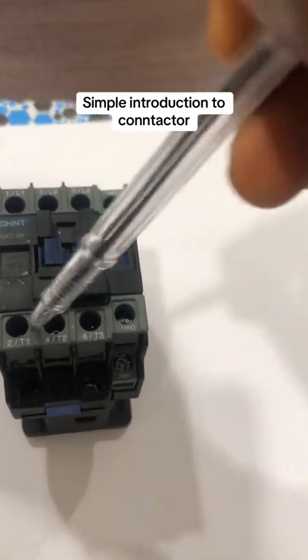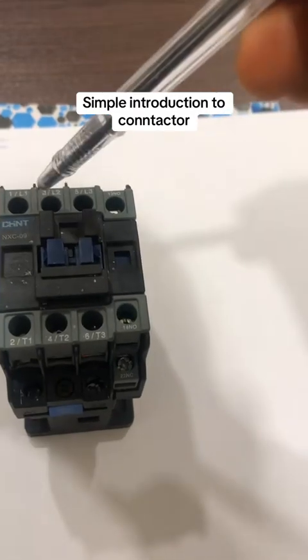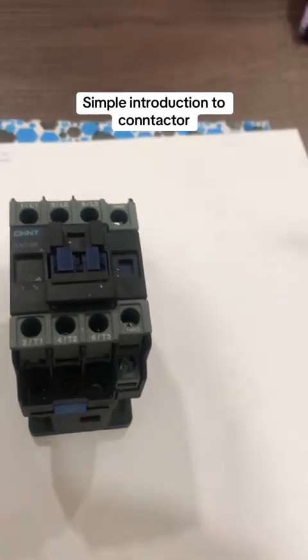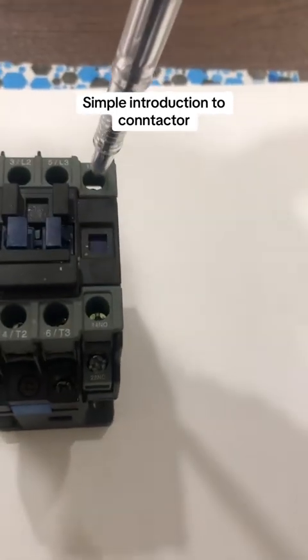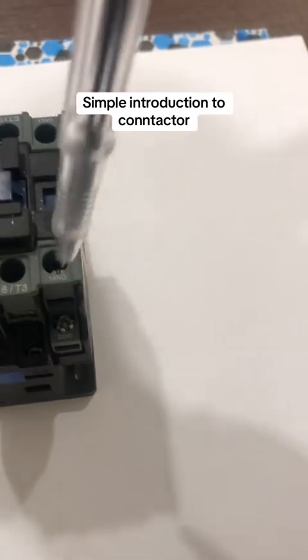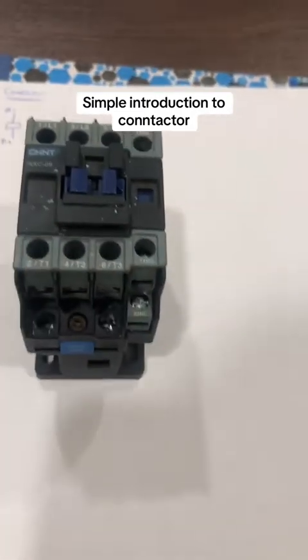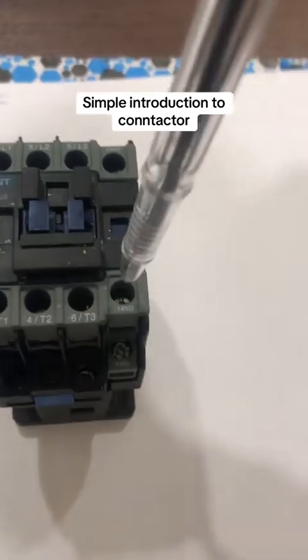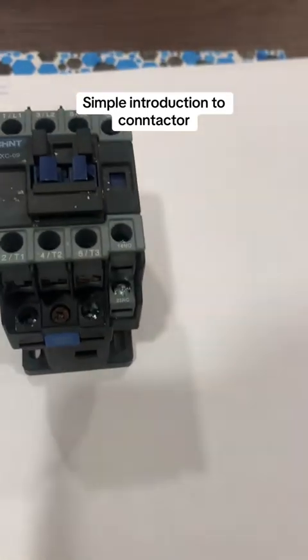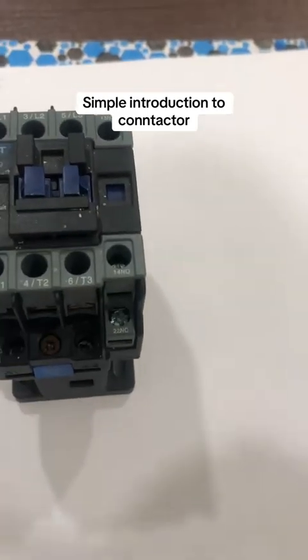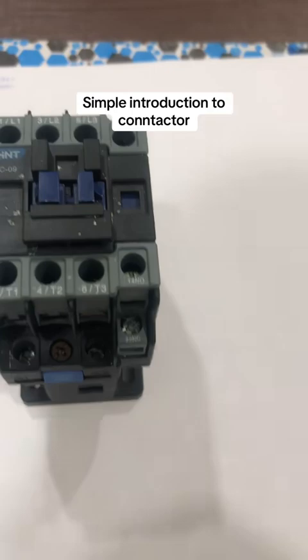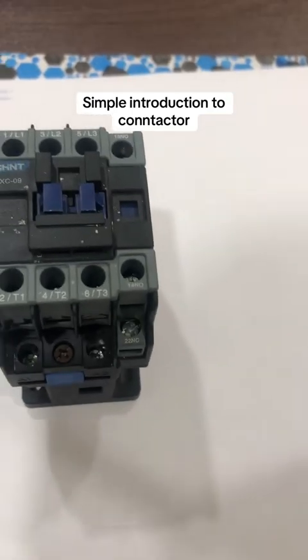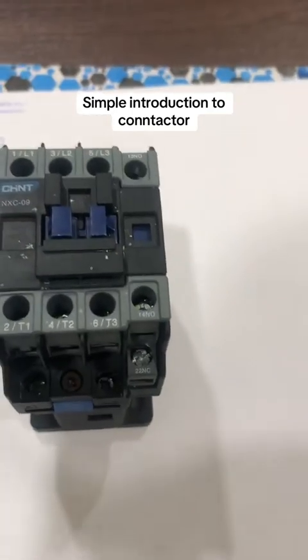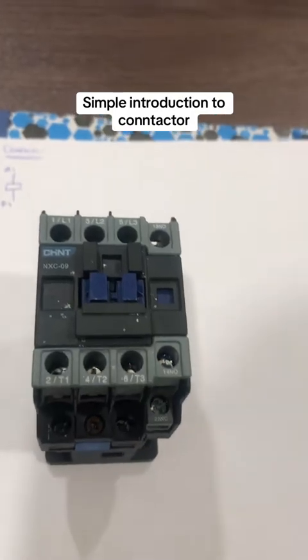These three contacts represent power, which can be used to easily control an electric motor, while pin number 13 and number 14, where you see the normally open contact, is for the control. This is where you connect your push button. In my next video, I'm going to explain, with the help of a push button and a load, how you can use the contactor to control a load.